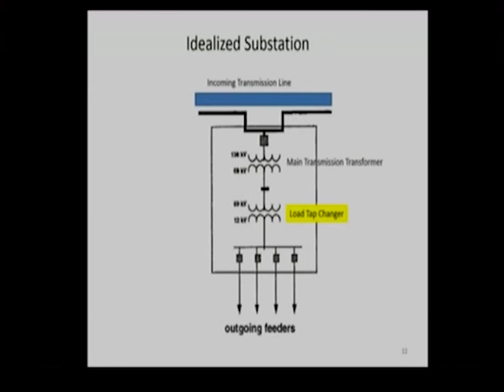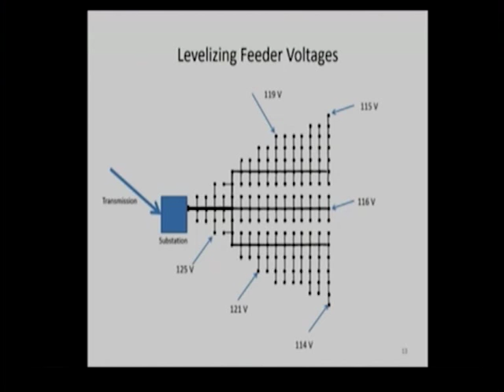And I'm showing here what you might typically see if you went out and put meters at all the houses on a distribution grid. Close to the substation, you'll see higher voltages, like 125 volts. When you get out to the end of the feeder, you'll see much lower voltages typically, and those could be down in the 114, 115 volt range. So in a high load situation on a very hot day like today, when everyone's running their air conditioners, those voltages will even sink lower.